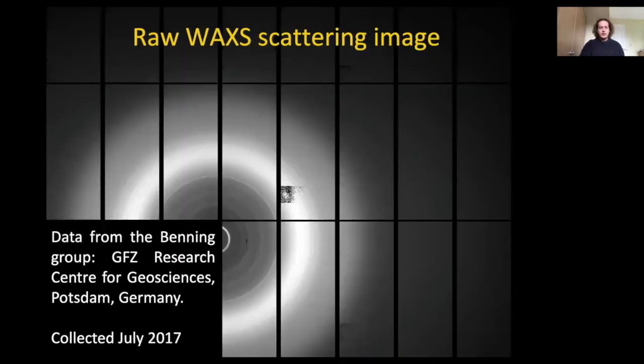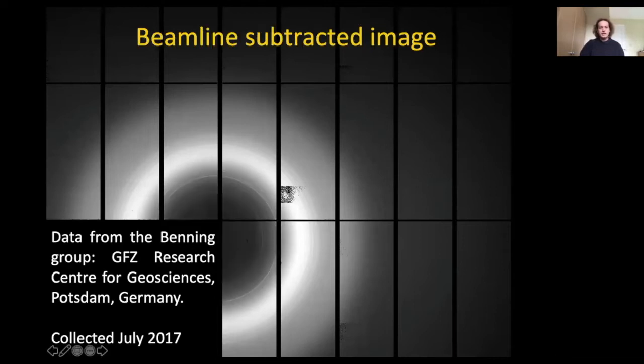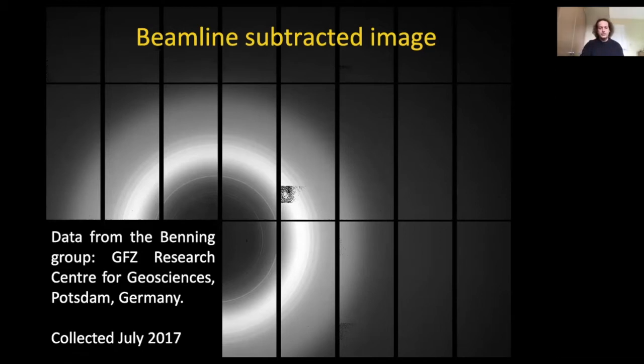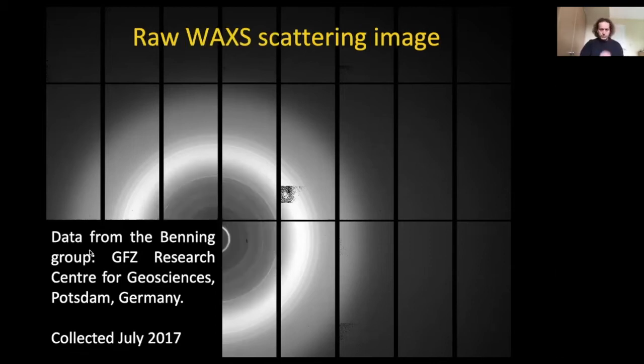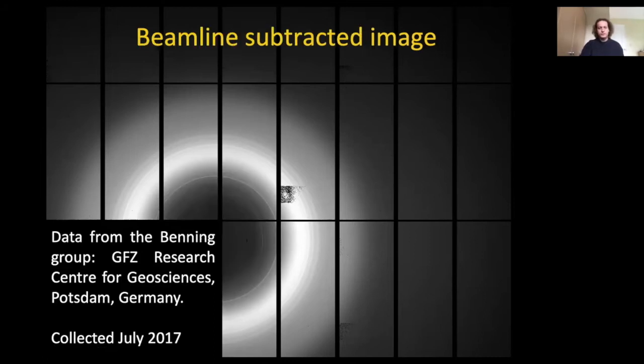Going back to the scattering pattern, after performing our first set of corrections and doing our first subtraction, there is a subtle change visible near where the beam center was. For I-22, this corresponds to the Kapton windows on the entrance to the wide angle detector and on the exit toward the small angle detector — the Kapton scattering rings visible in the original pattern have now been clearly removed.